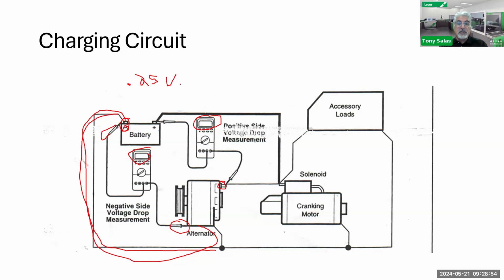If you see half a volt, like some manuals I've seen say of allowable voltage drop, in my opinion, you're too high at half a volt. But again, 0.25 volt is very important. So if I see greater than 0.25 on the ground side, that's telling me I have a high voltage drop.